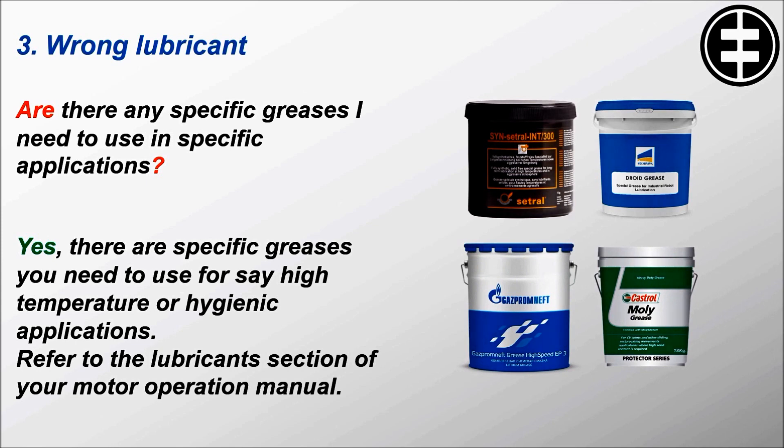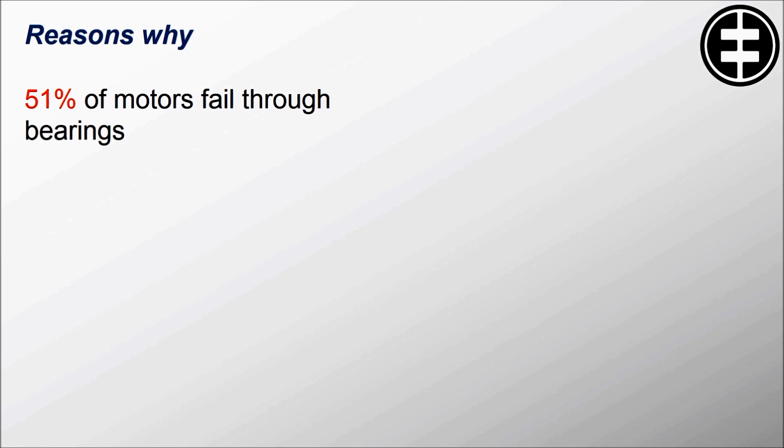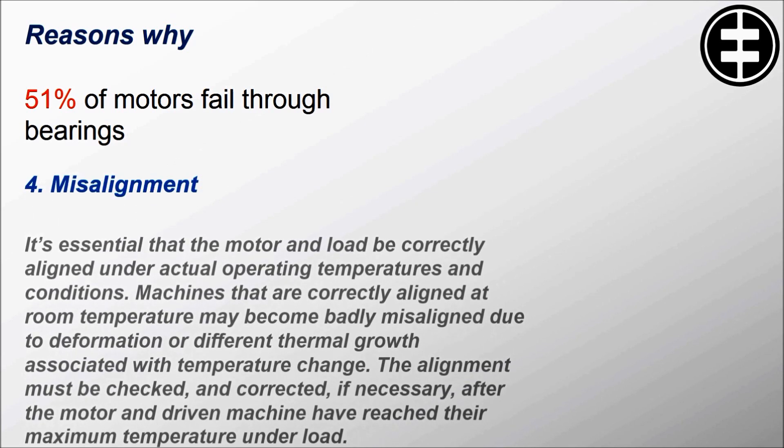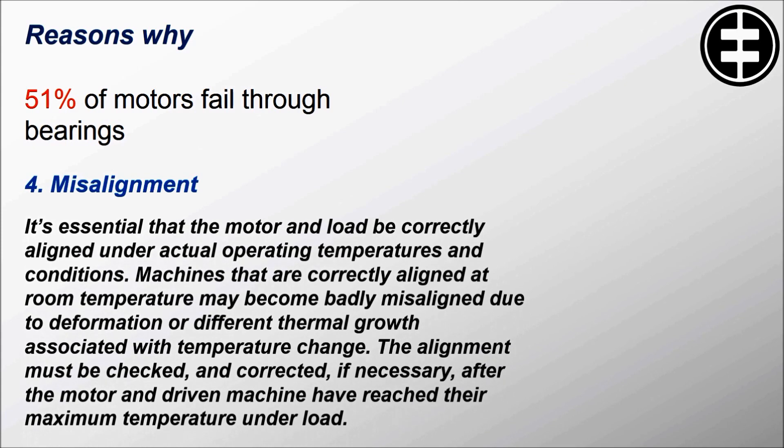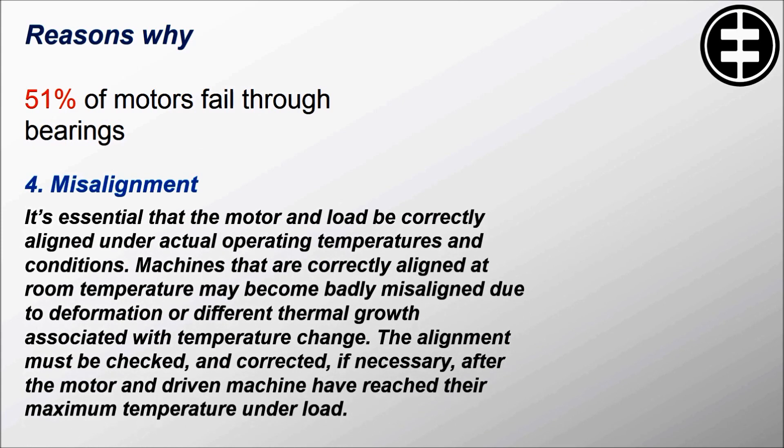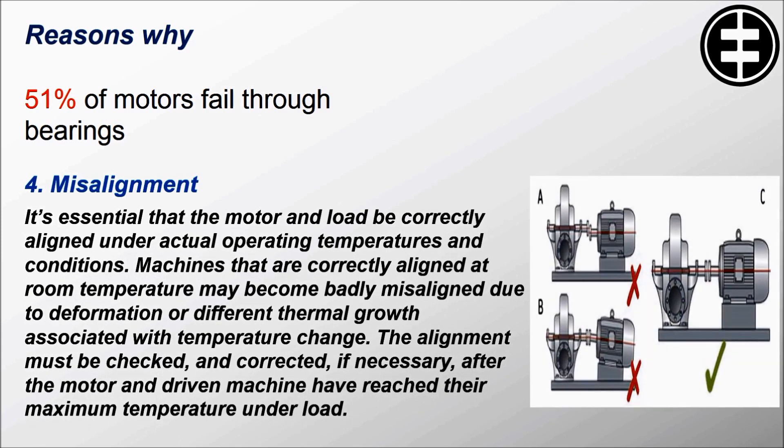Reason number four is misalignment. It's essential that the motor and load be correctly aligned under actual operating temperatures and conditions. Machines that are correctly aligned at room temperature may become badly misaligned due to deformation or different thermal growth associated with temperature change. The alignment must be checked and corrected if necessary after the motor and driven machine have reached their maximum temperature under load.